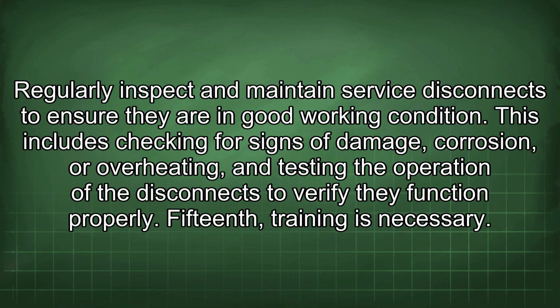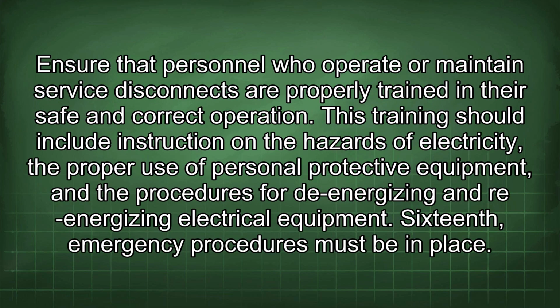Regularly inspect and maintain service disconnects to ensure they are in good working condition. This includes checking for signs of damage, corrosion, or overheating, and testing the operation of the disconnects to verify they function properly. 15th, training is necessary. Ensure that personnel who operate or maintain service disconnects are properly trained in their safe and correct operation.